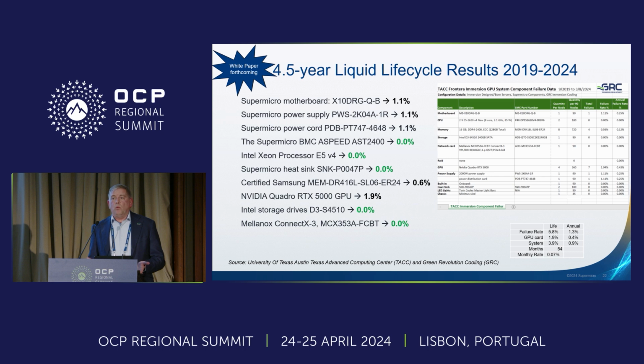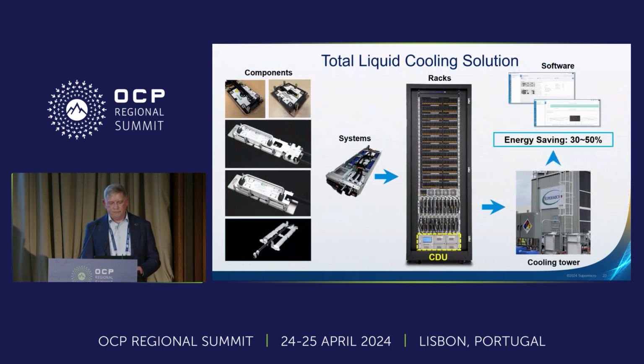It ended up being about a 1% annual failure rate in immersion circa 5 years ago, before anyone really knew what they were doing. We've been getting progressively better over the past 5 years, so we anticipate much lower failure rates than people have generally expected from immersion cooling.